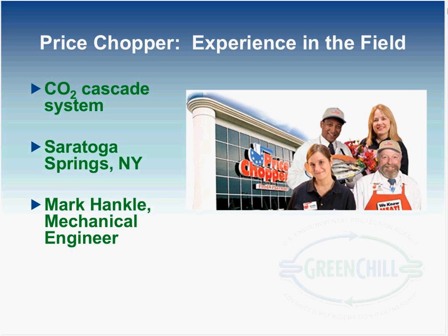Thanks, Keely. I guess a lot of what I'm going to say is a repeat of what Wayne had said. To date, we haven't had any leaks on the primary side of our Cascade system. We reduced our refrigerant charge 50% at that store on that system. Sorry, Mark, can you just briefly tell us how long the system has been in operation? Yeah, Saratoga's been running for a little over 2 years now. It started up in March of 2008. The store actually opened in June of 2008.